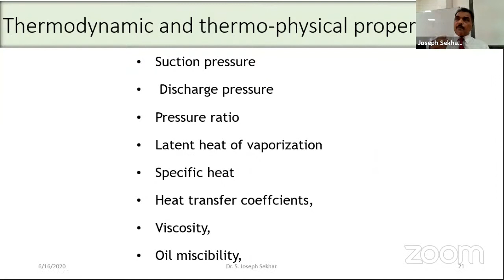The refrigerant should be compatible with system materials. For example, if we use ammonia, we should not use copper, because ammonia with copper causes caustic embrittlement and the system will fail. We also have to use proper dielectric material in the compressor — dielectric strength is important, otherwise there will be a short circuit and the system won't function well.